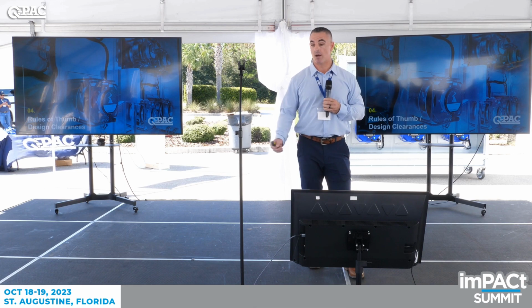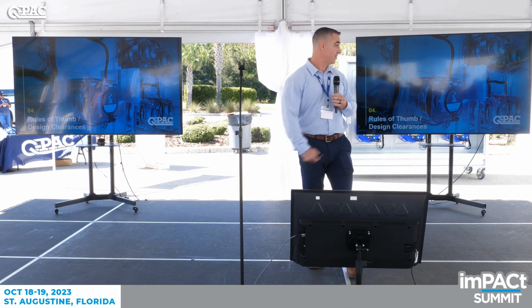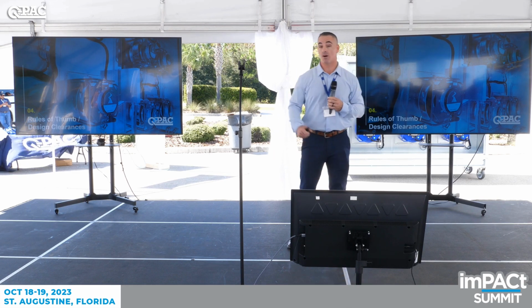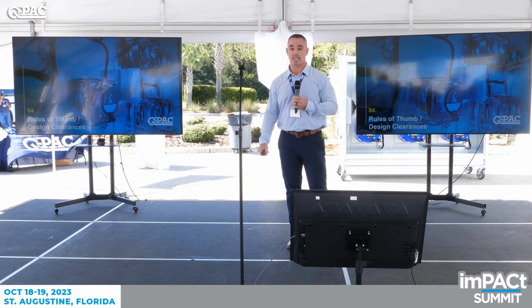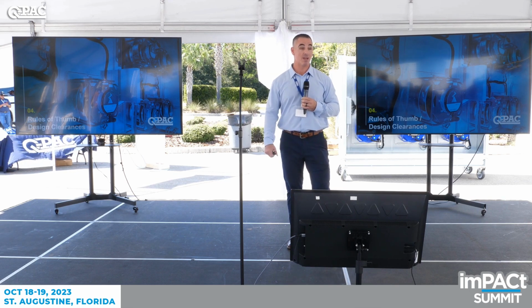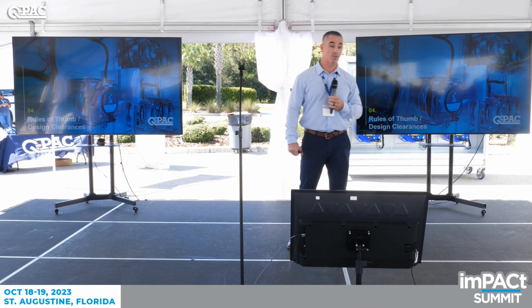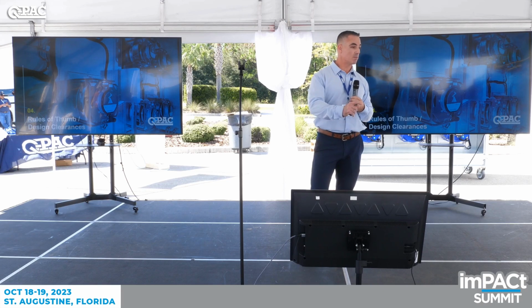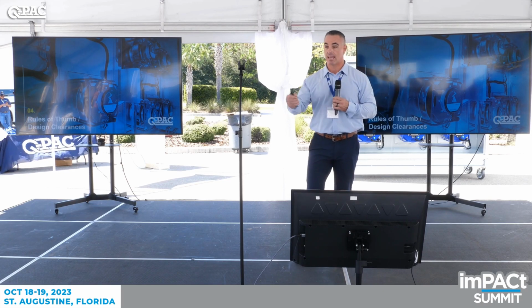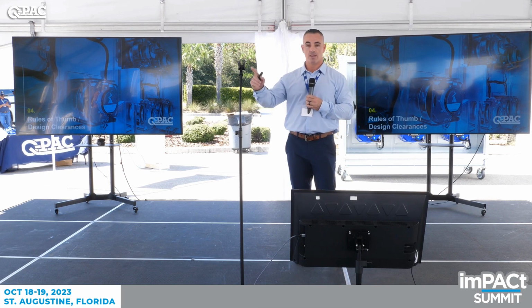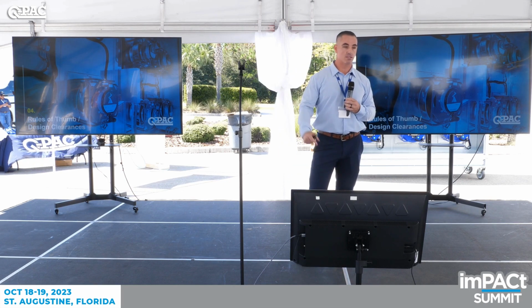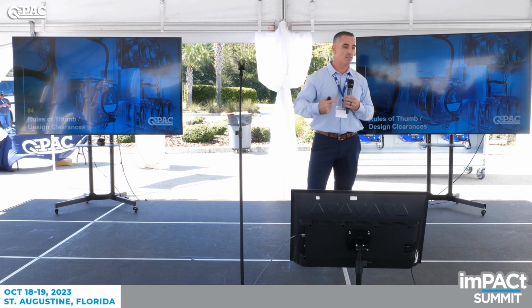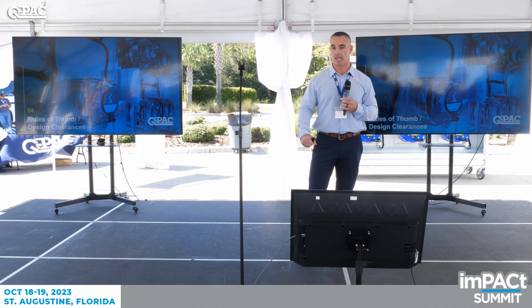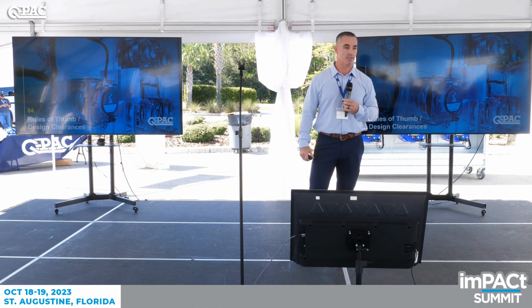So I have no problem telling owners — I've done several at hospitals, at OR rooms. We shut down at 10 or 11 o'clock at night, and we're up and running by 7 in the morning with airflow. We may not be under full control with the way we do it, but with hand mode and a potentiometer, you can get airflow, and then controls can come in later to hook up the controls and do what life safety requires.